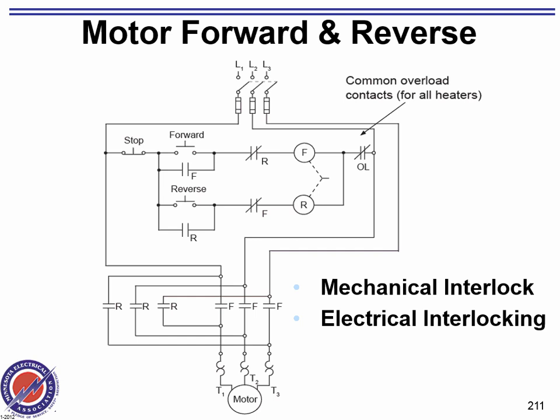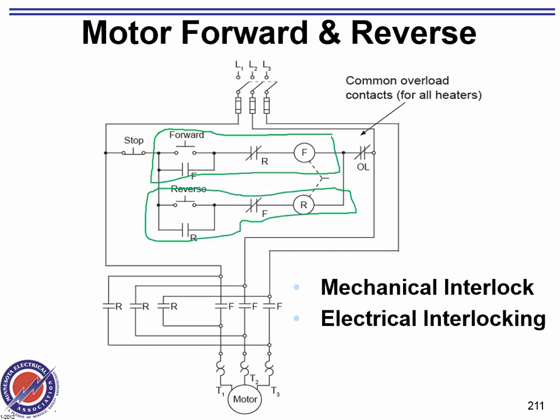Okay, now how do you reverse a three-phase motor? You have two magnetic contactors. You wire them as shown. So you have a circuit. Here's my forward magnetic contactor. Here's my reverse magnetic contactor. Can you guys see that? Then here's what you have, gentlemen.